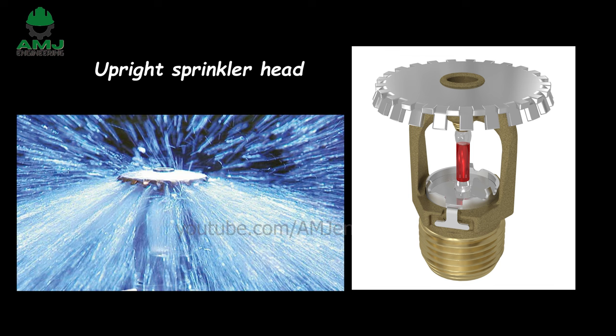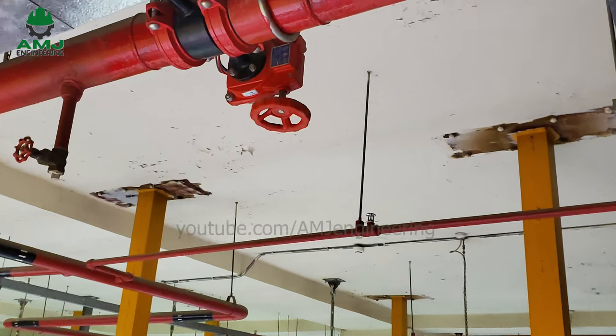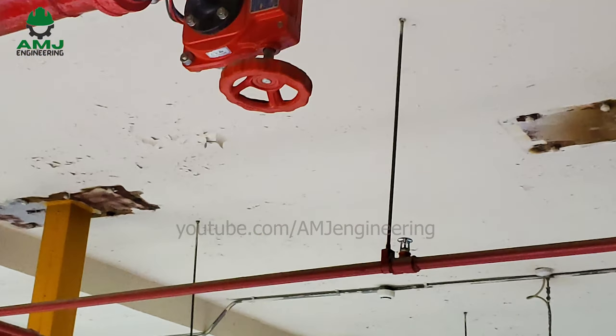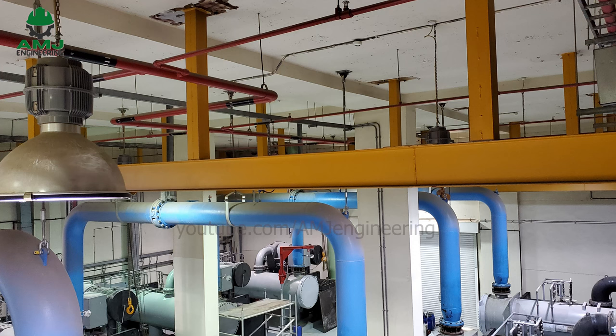Upright sprinkler head. Upright fire sprinklers spray water upward to a concave deflector, like an umbrella, producing a dome-shaped spray pattern. Rather than descending through the ceiling, these sprinkler heads are usually mounted on pipes just below the ceiling. Upright sprinkler heads are efficient at dispersing water between obstructions, and are frequently used for rooms that are inaccessible, such as mechanical rooms, warehouses, and industrial spaces. They are also often applied in structures with open ceilings.